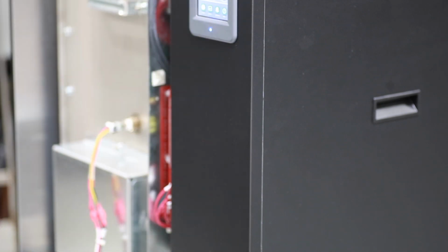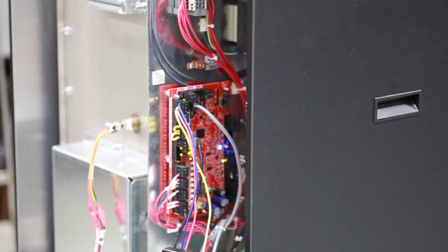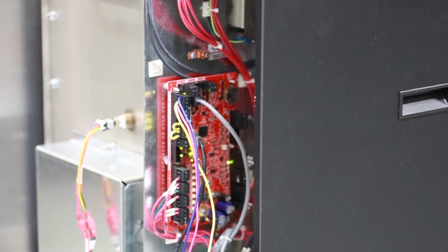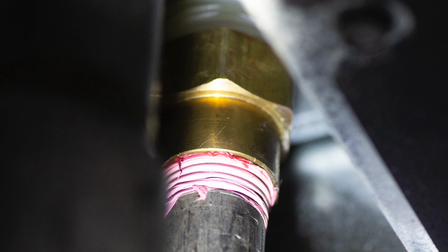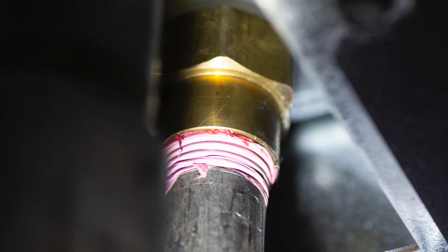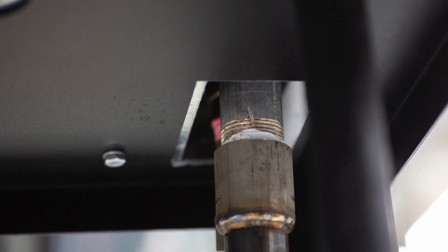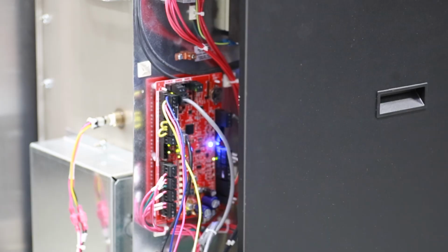Now we'll walk through the components and connection points you'll be looking at when performing maintenance. Downstream devices communicating with VaporLogic controller, demand signal from transmitter, high limit controller, airflow proving switch, water supply connection for tap, softened, RO or DI water, water drain connection. 1-stage and 2-stage connections are located underneath the unit. 3-stage and 4-stage connections are located on the right side of the unit. A standard maintenance visit for the RTS humidifier will take about 1 to 4 hours. Unit size and other factors will affect the amount of time required.